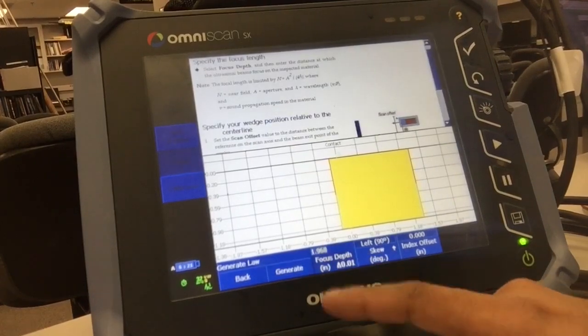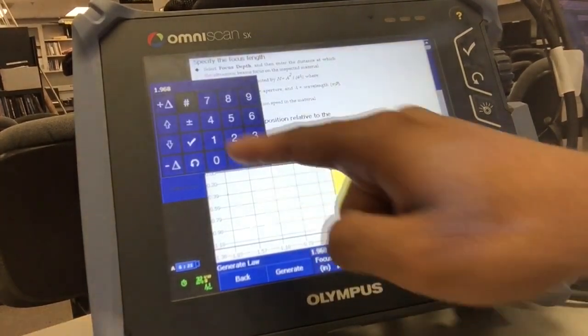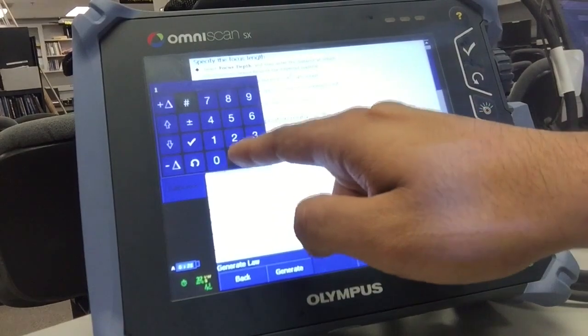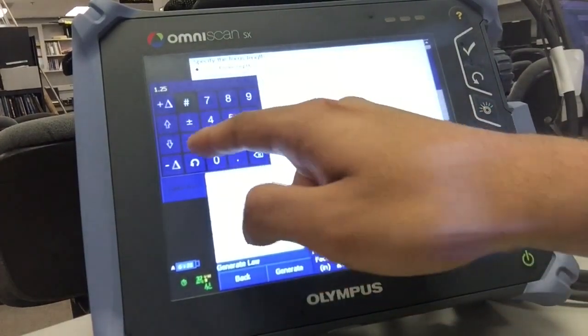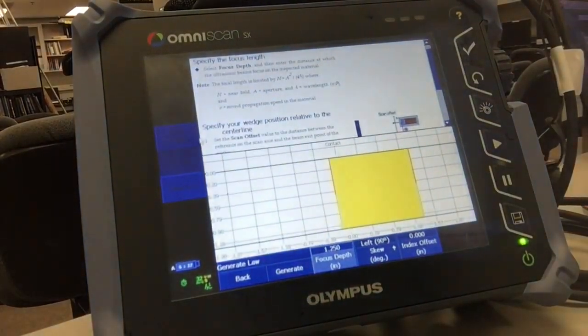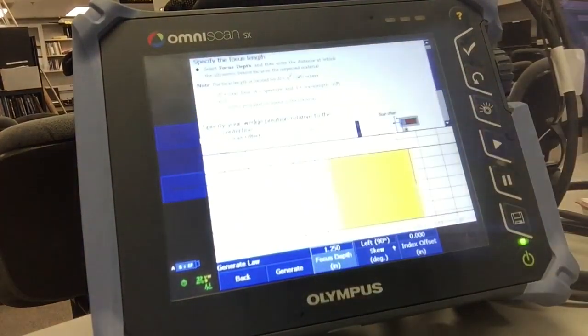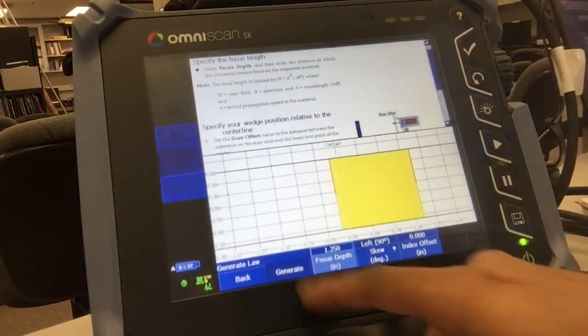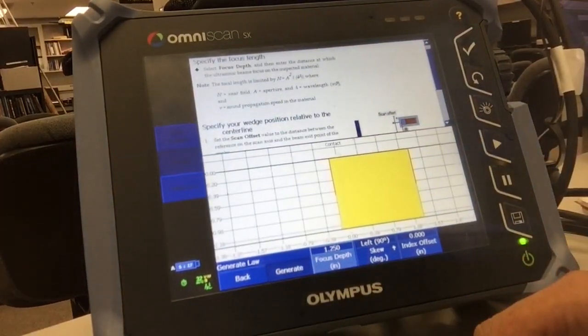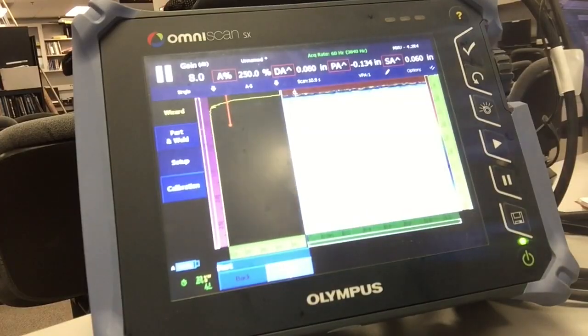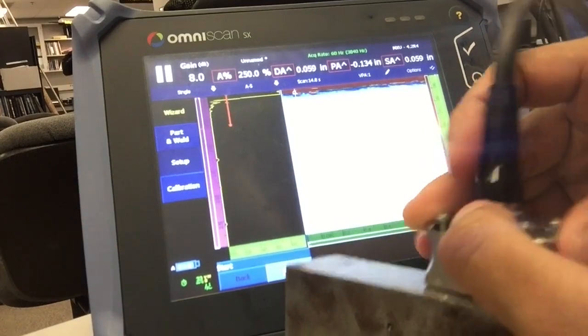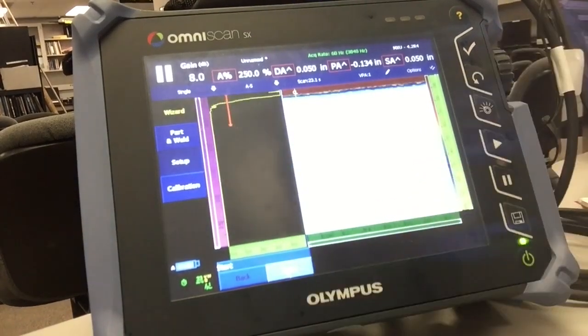Focus depth, I'm trying to get a signal off of 1¼ inch deep, so I'm going to leave my focus depth at 1¼ inch deep, just because I want to focus on this calibration block. That's it. Click Generate. The next thing I'm going to do is put some couplant on my calibration block and try to get a back wall from this calibration block.